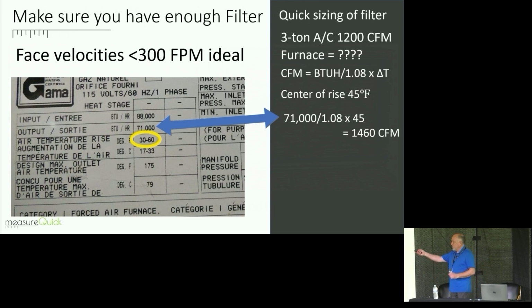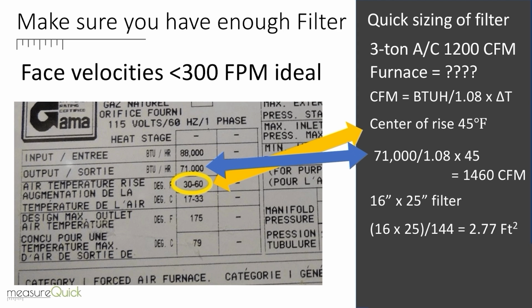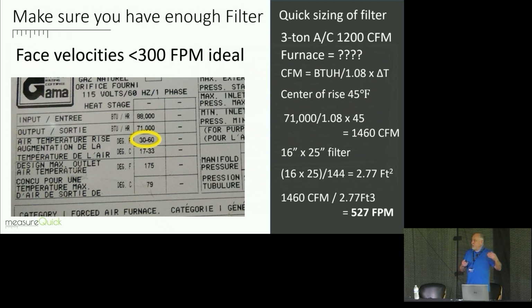So you start doing a quick check of the furnace, it's 1460, 16 by 25 filter, so you just take 16 times 25 divided by 144, that gives you square feet. It's going to tell you that that's 527 feet per minute. Anything in excess of 300 feet per minute is too fast, right? If it's over 500 feet per minute, you really do need to address it. But all filter manufacturers go, wait a minute, I got a 4-inch filter on there. Doesn't matter. The reason you have thicker filters, so if you think about like HEPA, it's more restrictive. So you need more surface area to have that low pressure drop, but it has nothing to do with the filter face velocity.